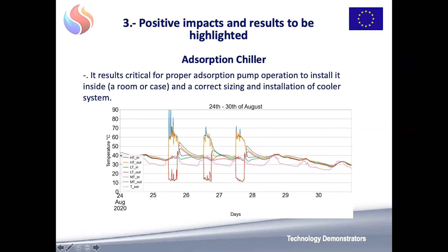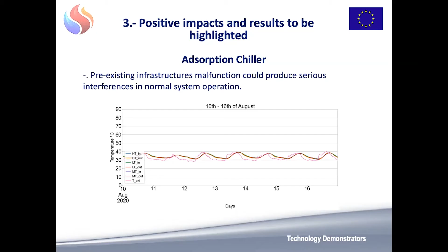Regarding some more technical difficulties we had during operation, we were really getting crazy about the interferences with the rest of the system, especially with the three-way valves that connected the hot water circuit with the cold water circuit. It had to be really properly fitted to avoid pouring hot water into the cold water circuit, because that is absolutely critical.